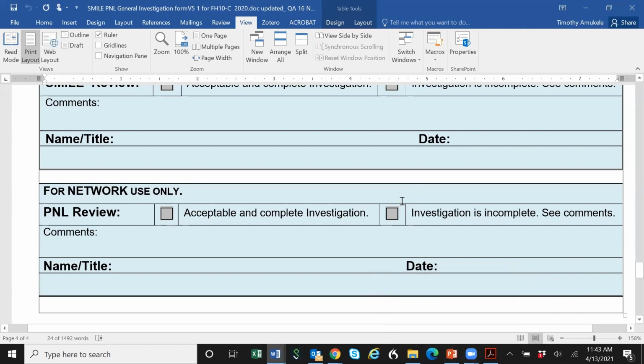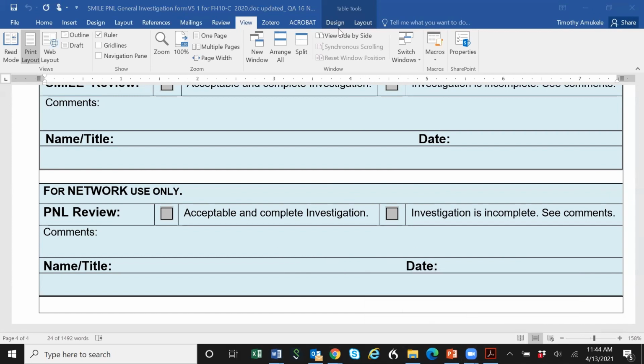Okay, so actually on that last point, I'll jump down to this question. There's a clinical chemist or a chemistry lab with experience with EQA where it was a worldwide EQA, so participants from all over. And it was discovered that whenever they were compared to the worldwide data, they noticed failures, but the same report when just compared with regional participants within the same scheme, the results were acceptable. Difficult to do corrective action. Is there a way to mitigate such scenarios?